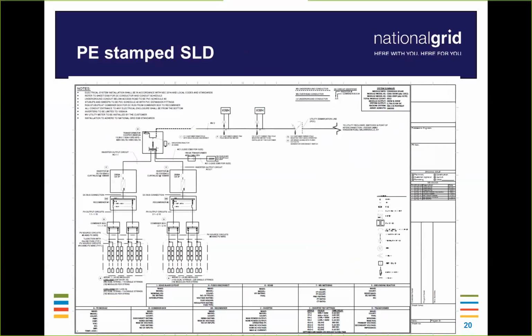So when we get into, for instance, transformers, knowing that transformer's configuration, if it's a delta grounded Y, YY transformer, or whatever type of configuration the transformer might be, that type of information should be represented on the drawing. The impedance of the transformer should be represented on the drawing, as well as the size. For fusing characteristics, the type and the size of the fuse should be identified. And other general characteristics that would describe ratings or size for overcurrent protective devices or switching devices should be represented on the drawings, as well as naming designations.